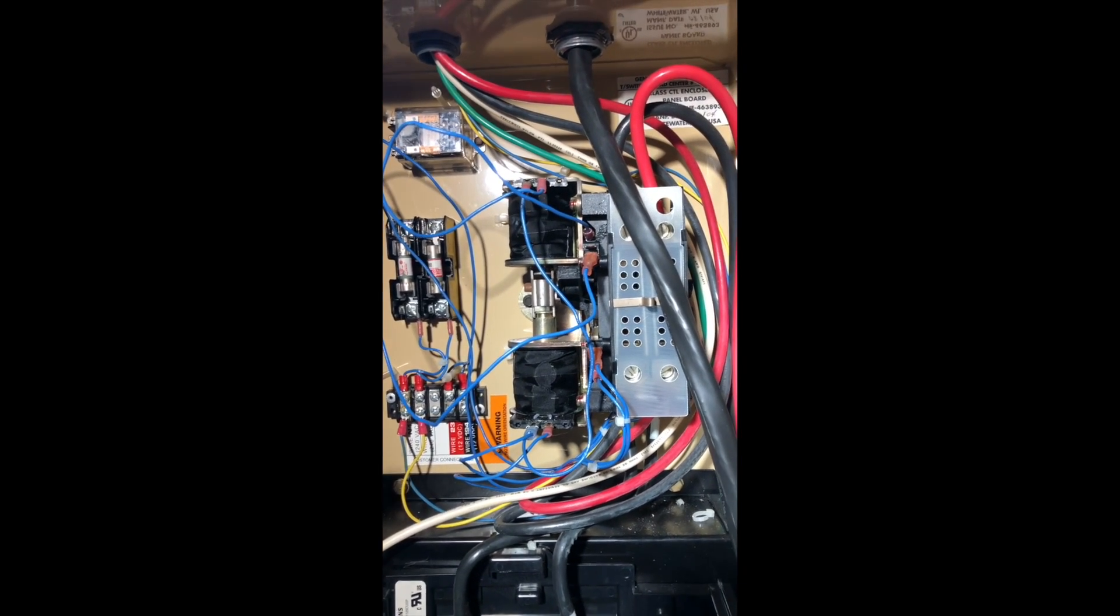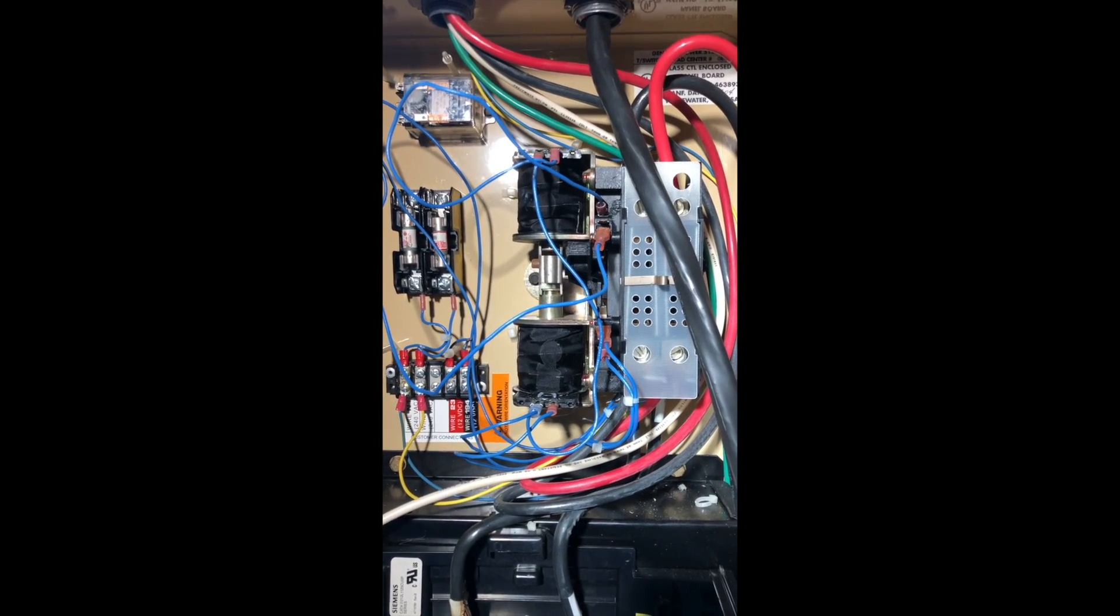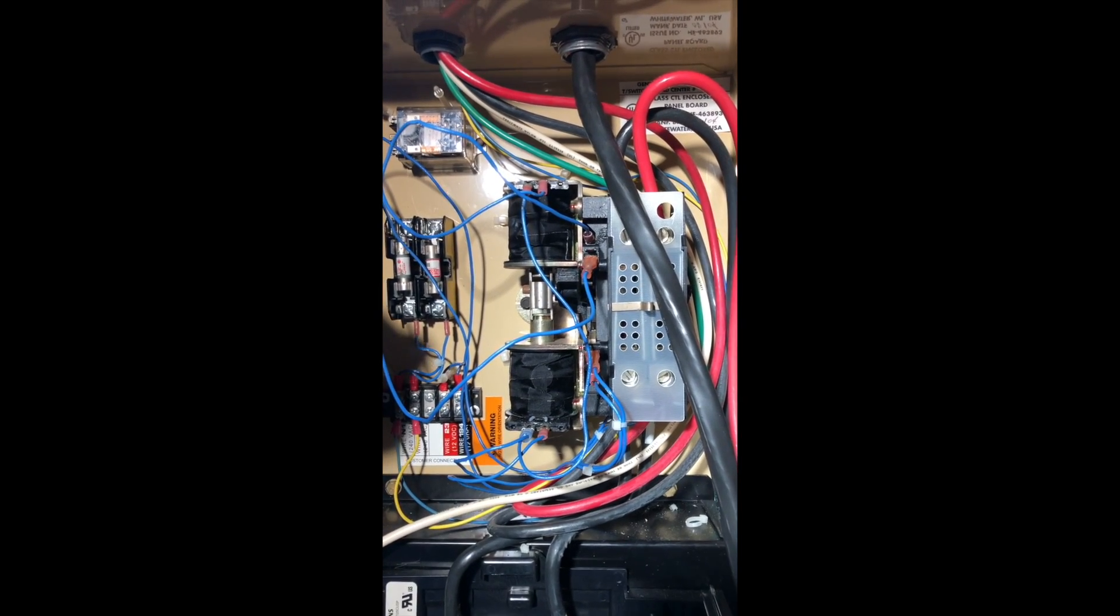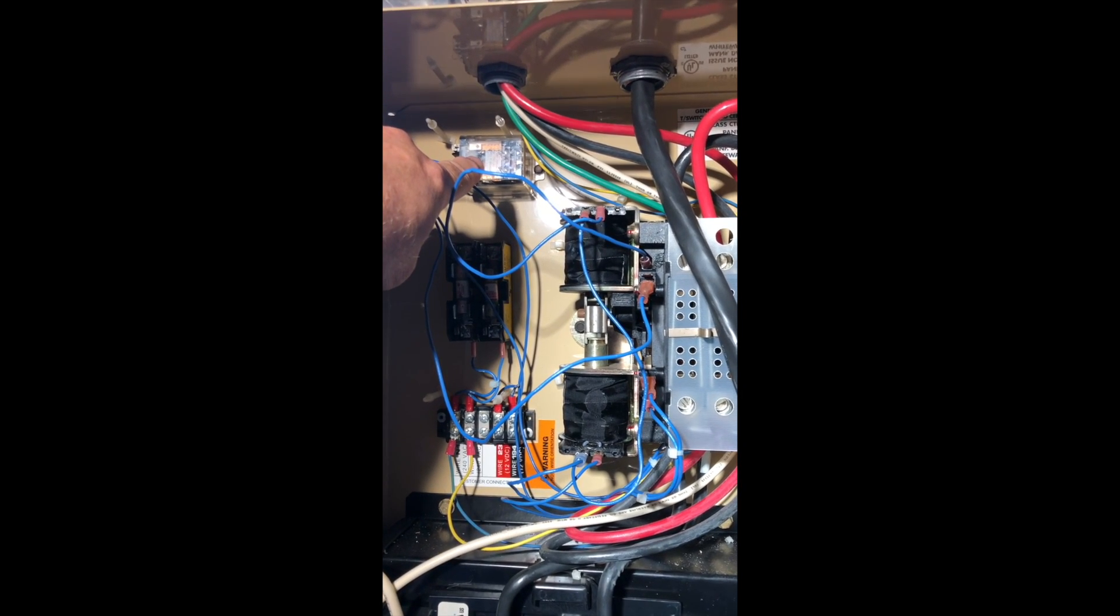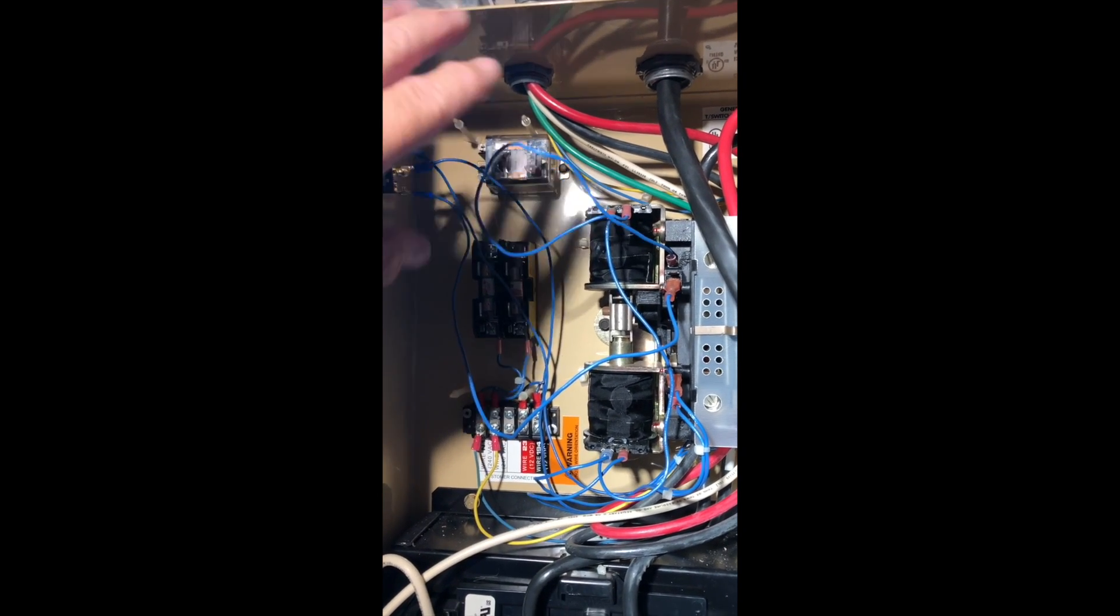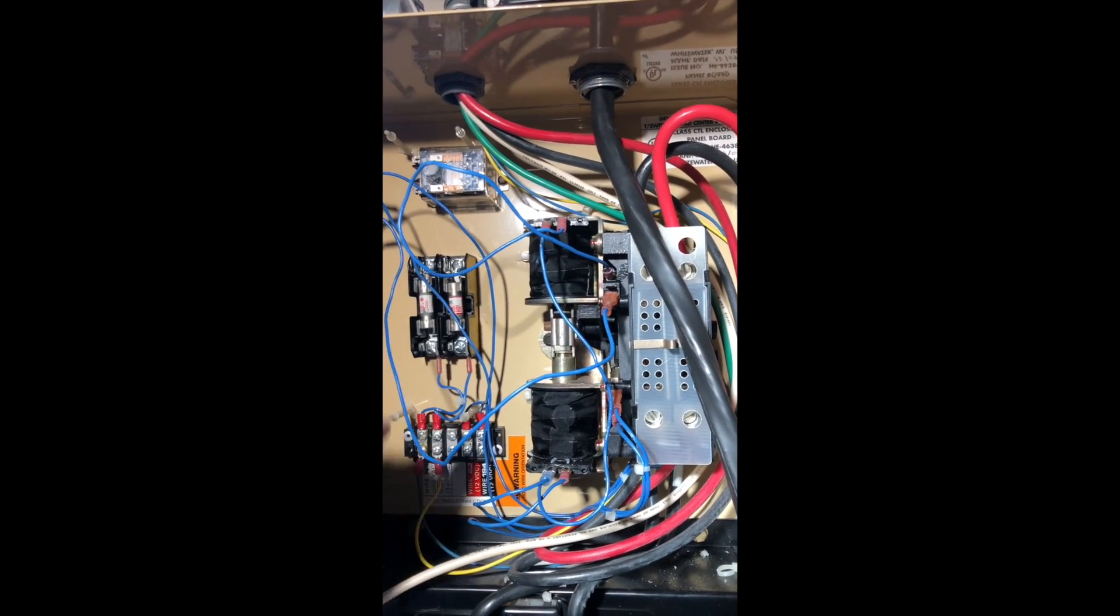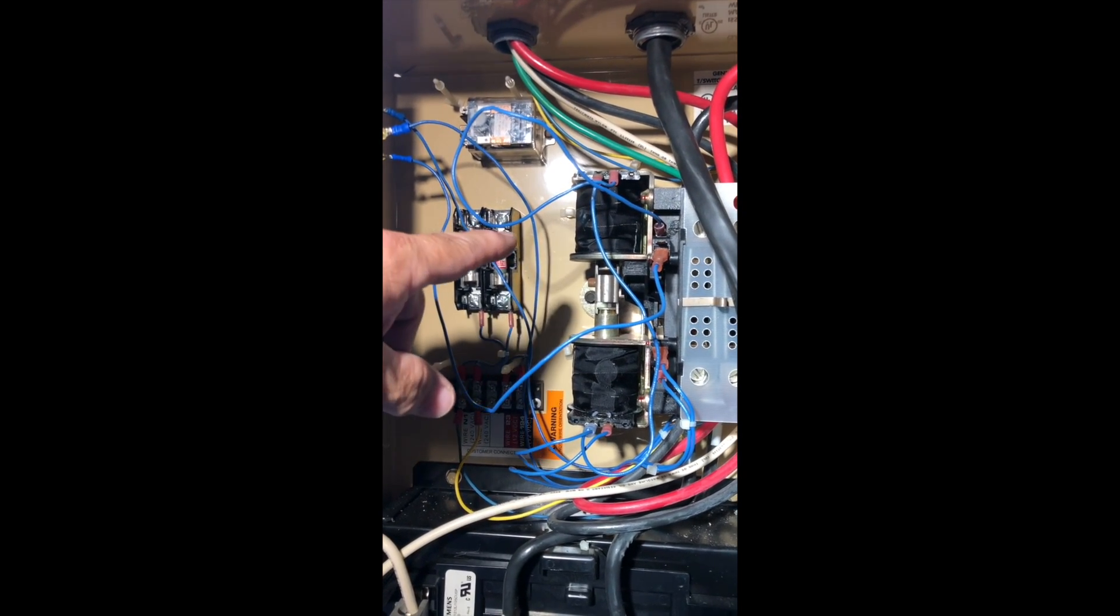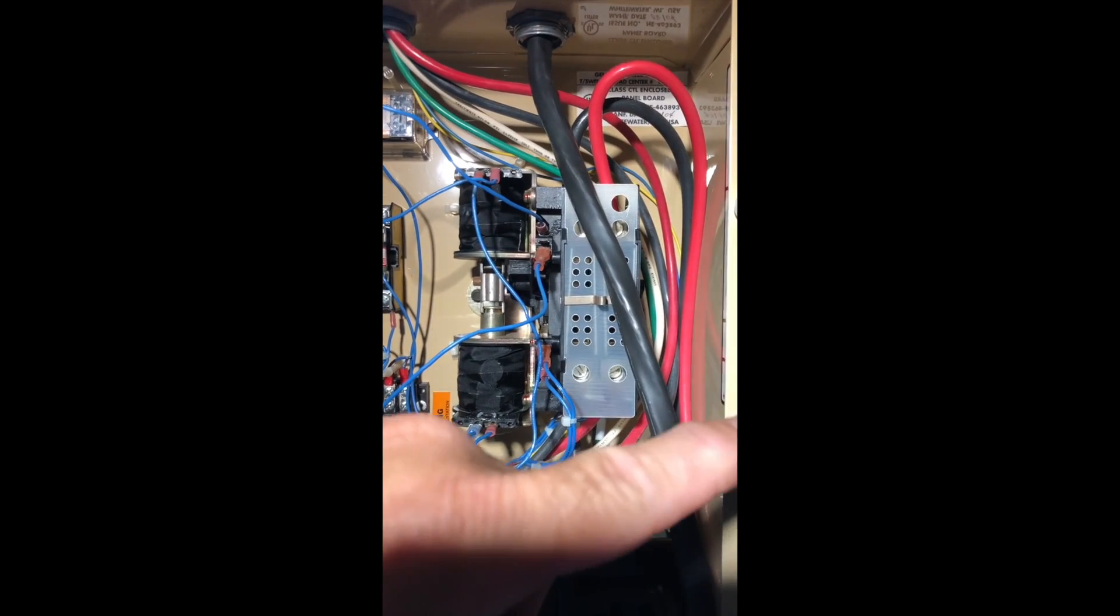All I did was isolate what fires the electromagnets that move the plunger up and down. Right now, this panel is dead, so that's why I have my hands in here. Basically, there's a relay up here which is 12 volts, and also it has an AC side. That's the relay's job - to work with the generator logic board, which is way above my pay grade and it's also gone because it's part of the generator. That would sense whether or not you had stable power coming in from your generator, and after a few seconds, it would fire the switch and switch you over to generator. And then when your mains came back on, it would do the same thing in reverse.